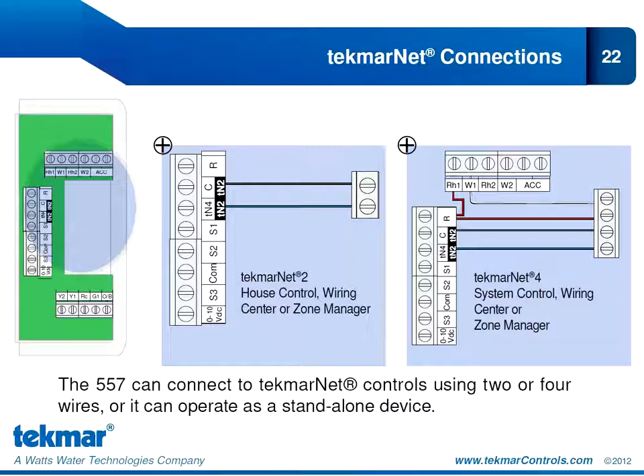Now, tekmar has 2 lines of communicating controls. We have tekmarNet 2 and we have tekmarNet 4. And in the past, thermostats were either TN2 or TN4. What's great about the 557 is that it can be both. You can configure the 557 for a tekmarNet 2 system. So we're showing 2 wires connecting to a TN2 house control wiring center or zone manager. Or we can connect the 557 to a TN4 system control, wiring center, or zone manager.